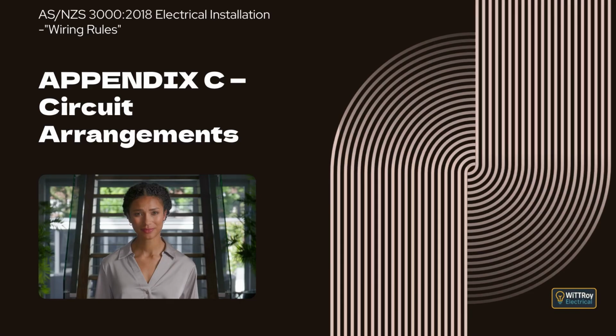This clause explains that any item of equipment with a current rating greater than 20 amps per phase must be connected to its own separate and distinct circuit. Where more than one item of equipment is to be connected to the same circuit, careful consideration is required. This includes how many points are supplied together, and what type they are, such as lighting, socket outlets, or appliances. It also includes how the equipment operates, recognizing that some loads vary during the day or by season.